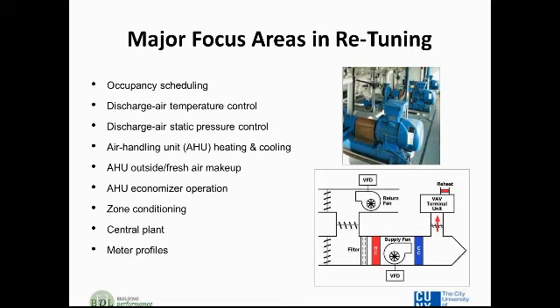So we have a building retuning measure having to do with discharge air temperature control, another one having to do with discharge air static pressure control, and one or the other may be favorable or useful to you depending upon your equipment setup, on whether or not you have VFDs on your supply fans and the like. Also, air handling unit heating and cooling. We talked about outside air, fresh air makeup, and looking at the level of ventilation that you're providing.